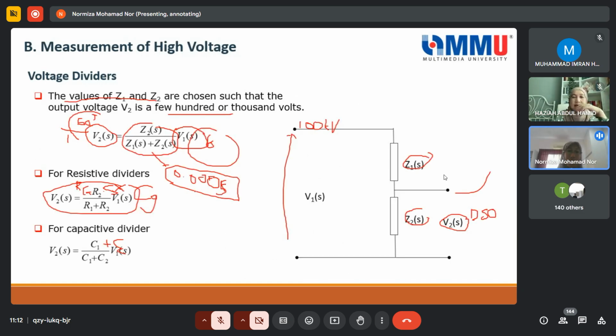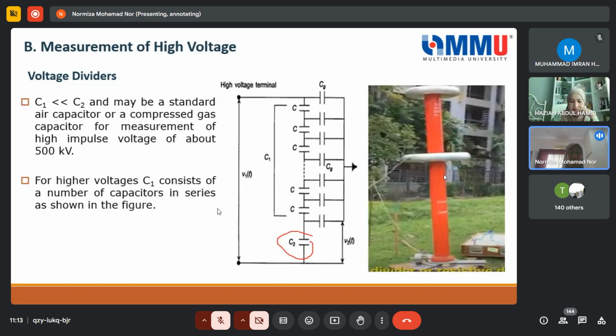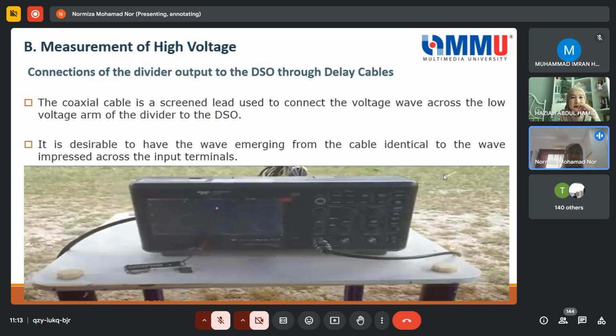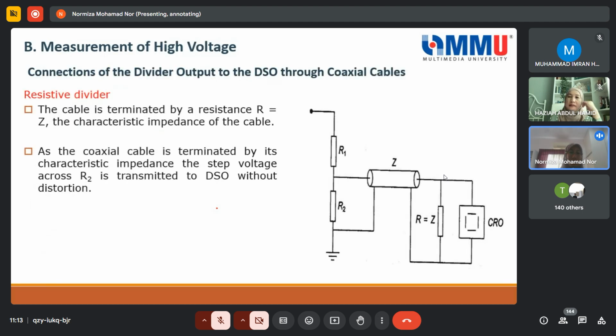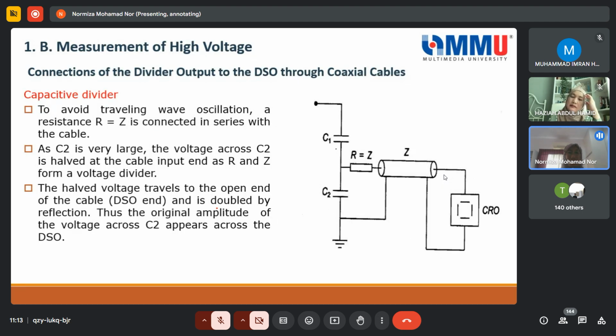Of course, when the designer designs or when we buy this divider, we use this ratio. But when we do the measurement, the cable and everything is no longer a concern of the manufacturer, because they provide the divider and they provide the ratio. When we do the measurement, we may not use the same ratio as what they suggested, because our cable has its characteristic impedance. So that's why the calibration test is very important.